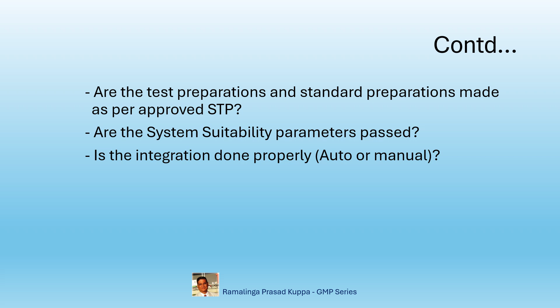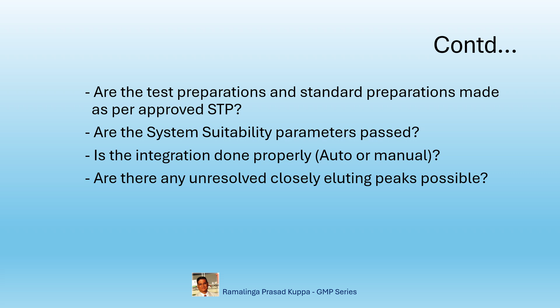Are there any unresolved closely eluting peaks possible? The overlapped unresolved peaks will give more area, leading to failures. This should be checked during the investigation. Are there any ghost peaks in the chromatogram that got integrated? Ghost peaks are another problem. It is necessary to check if any such peaks appear on the chromatogram.